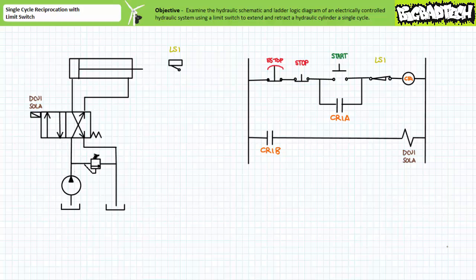To prevent the necessity of having to constantly hold this button down, the ladder logic includes a normally-open holding, latching, memory, or seal-in contact CR1A associated with control relay CR1 in parallel with the start push button in rung 2. The third rung consists of a normally-open contact CR1B associated with control relay CR1 in series with the solenoid DCV1 Sol A. Note that when the coil of control relay CR1 is de-energized, its associated contacts return to their deactivated state — both CR1A and CR1B will reopen.